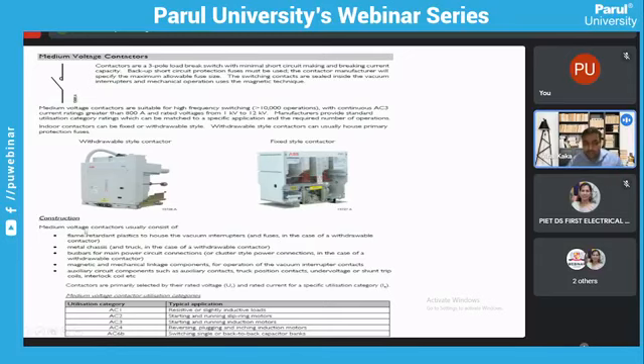Again, this is just a constructional point in terms of the medium voltage contactor. It is developed with flame retardant plastic to house a vacuum interrupter, a metallic chassis, busbars for the main power connections, and magnetic and mechanical linkages. Now there are also different types of designs from different vendors. From my experience, this is just shown with an ABB, but you might have heard about Eaton or other vendors. They have a type tested design where they use a fixed type contactor along with a 3-position switch from the bus bar, and then an external fuse connected between the bus and the contactor. So it depends on the design and how exactly the vendor has developed the product, but these are all accepted products across the market.